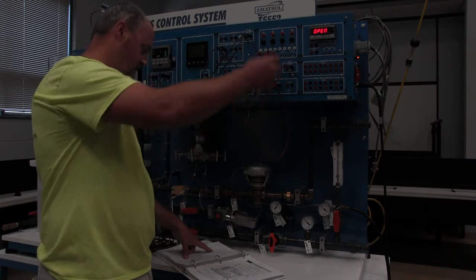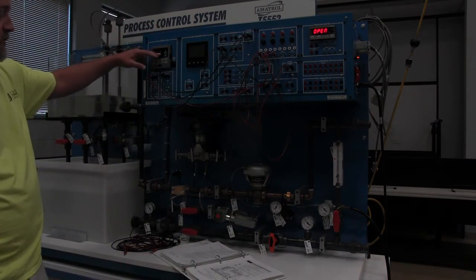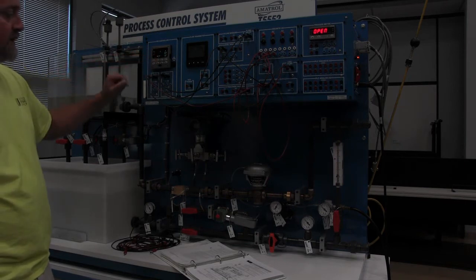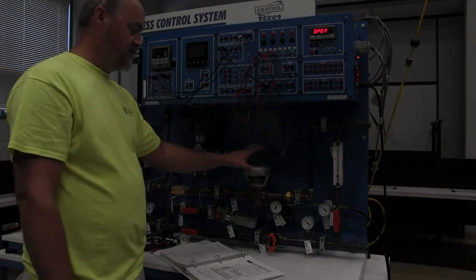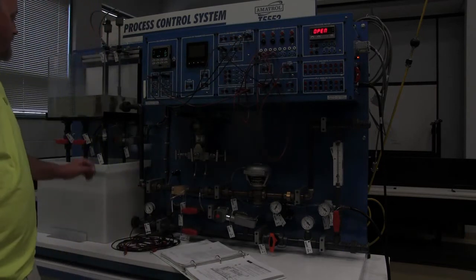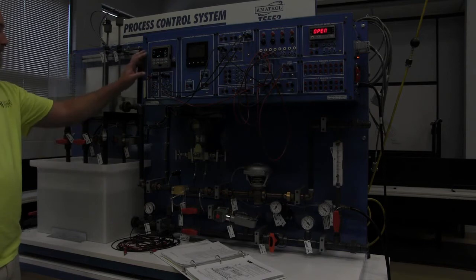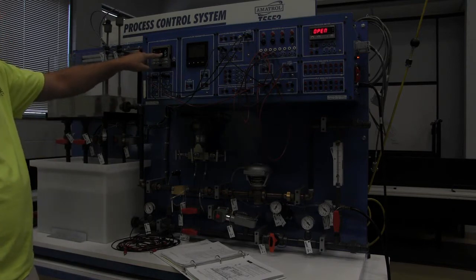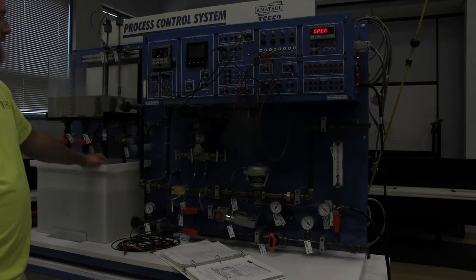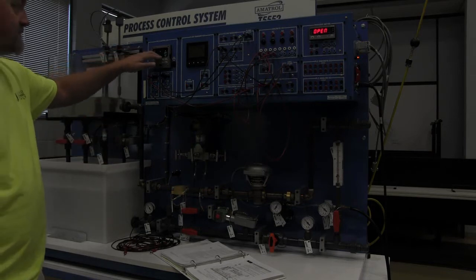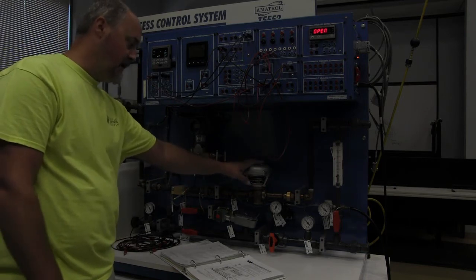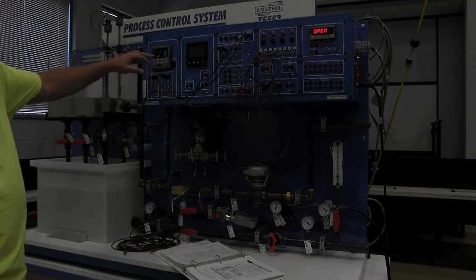So now if I was to turn on selector switch 2, which opens a solenoid valve, this level is going to start dropping. When this level starts dropping and it gets below that set point, it's going to say, hey, I need more water. This 4 to 20 is going to output to this valve saying open up some more. So now we have a solenoid valve on, which is now dumping water out. The level was decreasing. It went from a 3.3 to a 3.2. Now 3.1. Three point 0. 2.9. So now as this gets down below that set point, I can hear it. You can hear the air in this valve adjusting to try to maintain that 3.0 level.